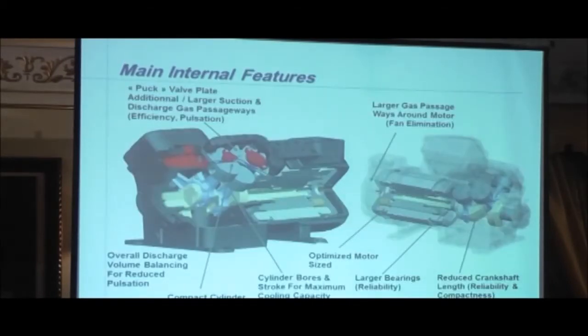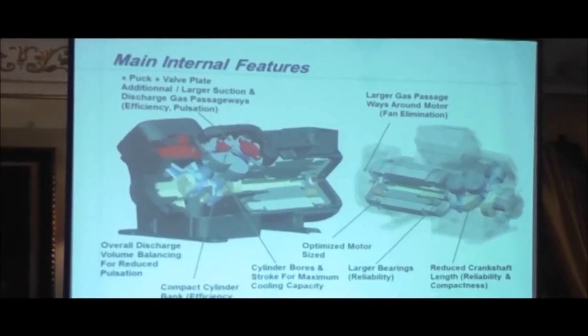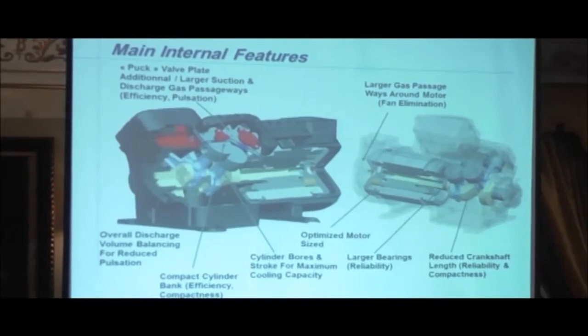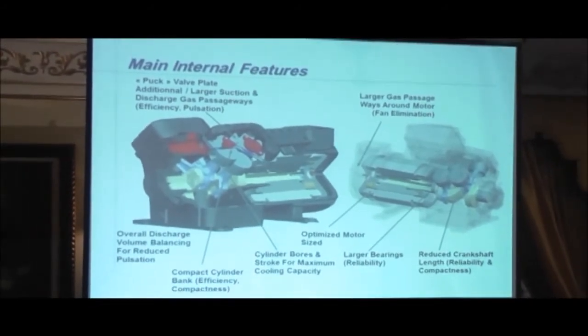So what has changed in the new compressor? Okay, the new compressor is more compact. Right? We've reduced the crankshaft. That increases reliability by reducing the length of the crankshaft. There are now larger bearings, so it can take higher loads. We've optimized the motor. The new compressor has a new arrangement of cylinder bore and stroke. Okay. We've modified the valve plate to increase the efficiency as well.